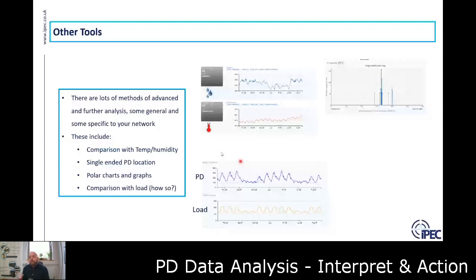There are lots of different methods and further analysis you can do with PD. A common one is looking at PD against temperature and humidity, because certain PDs can be affected by humidity and temperature changes — caused either by the load or the external environment. It's also useful to look at PD and load together: you can import load information, and as shown in the chart, there's a clear pattern where PD increases as load increases.